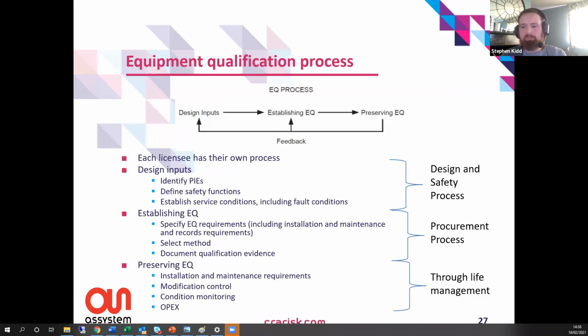So the equipment qualification process itself, in the IAEA guidance, splits into three main chunks. There's the design inputs. That's really the design and safety process that I've talked about, where we identify what can go wrong. We define the safety functions and the conditions that the equipment needs to operate in, including in fault conditions. Then there's establishing the EQ, which is where we talk about this effectively through the procurement process. We specify the requirements that are driven from the safety case in the plant specifications that go out to the suppliers. And they're ultimately demonstrated through qualification with appropriate qualification evidence.